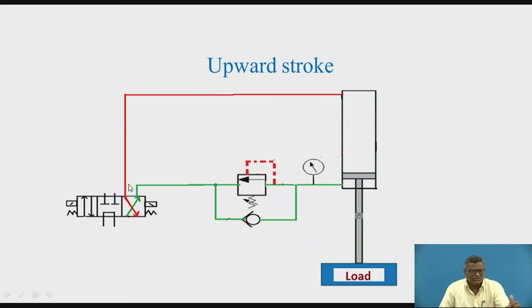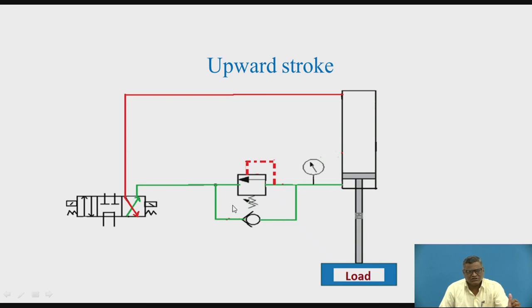The returning oil will come to port A, and A is connected to T at that time. Now the importance of the check valve can be observed. In the earlier situation when the piston was coming downwards, there was no use of the check valve. But in case of the return stroke, we are having the use of the check valve. P is connected to B, and the oil goes to the cylinder through the check valve only — it will not pass through the counterbalance valve but will pass through the check valve. It goes to the rod end and the piston is raised vertically upwards. The oil returning from the cap end goes to port A, and A is connected to T.